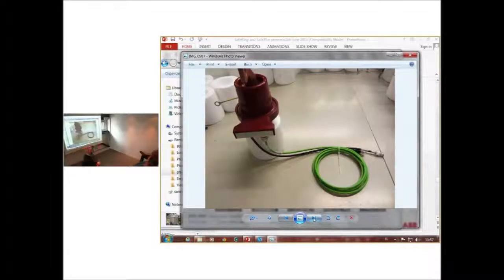And now we have some interesting devices with this bushing. As I mentioned very quickly, we have this combi sensor. The combi sensor means that in this one we have a capacitive divider and a Rogowski coil, and with this green cable you can take this RJ45 plug and plug it into a relay, and then you can measure voltage and current linearly with a relay. The accuracy is not 0.2S for the medium voltage, but with calibration you are at 0.5. So it's very good and very compact. So one of these then replaces one VT and one CT, if you need to keep control over the load flow in the network.